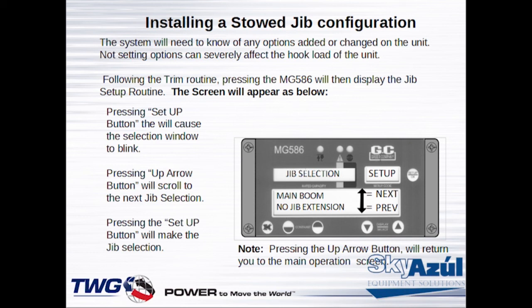This is the last step in the calibration procedure, and when it comes up, it's going to say jib selection on it. If you press the setup button, this will start blinking. When it does, if you use the up arrow key and start rolling that, it will cycle through different jib setups - it'll say 26-foot jib, 26 to 46-foot jib, or whatever it is. When you reach the one you want, you press the setup button again, and it will lock that procedure in. When you go to the operator setup screen, you'll be able to call up the jib. It kind of causes some havoc the other way, because when the operator presses it, he can't get to the jib - I used to get panic calls on that.